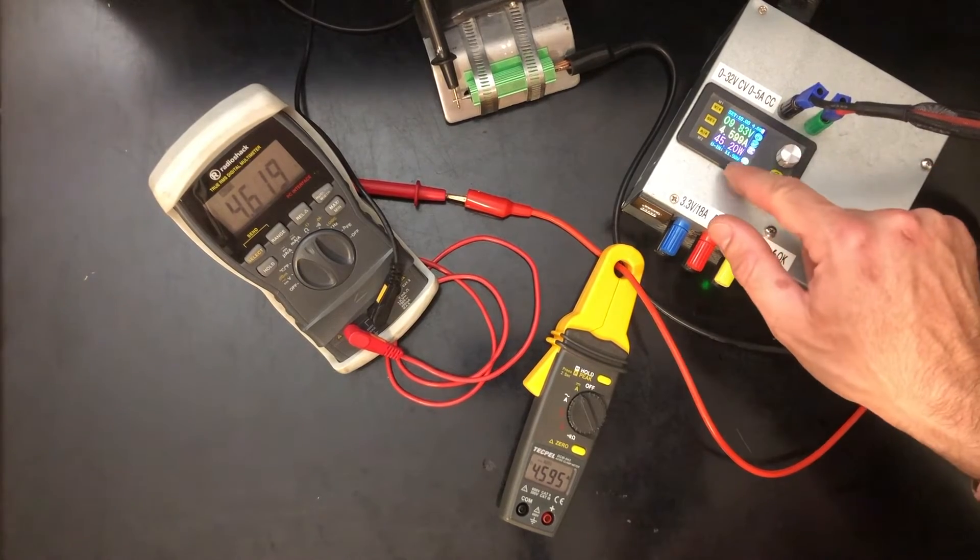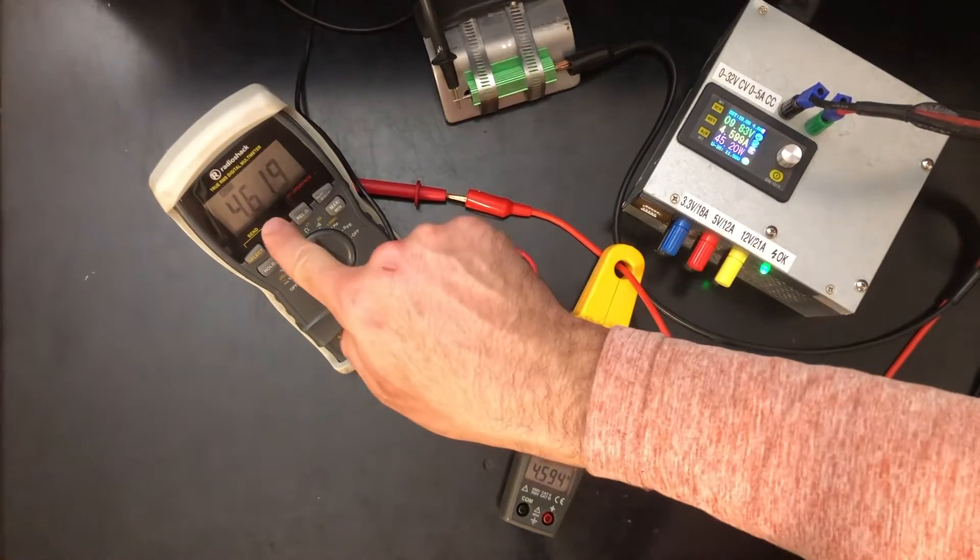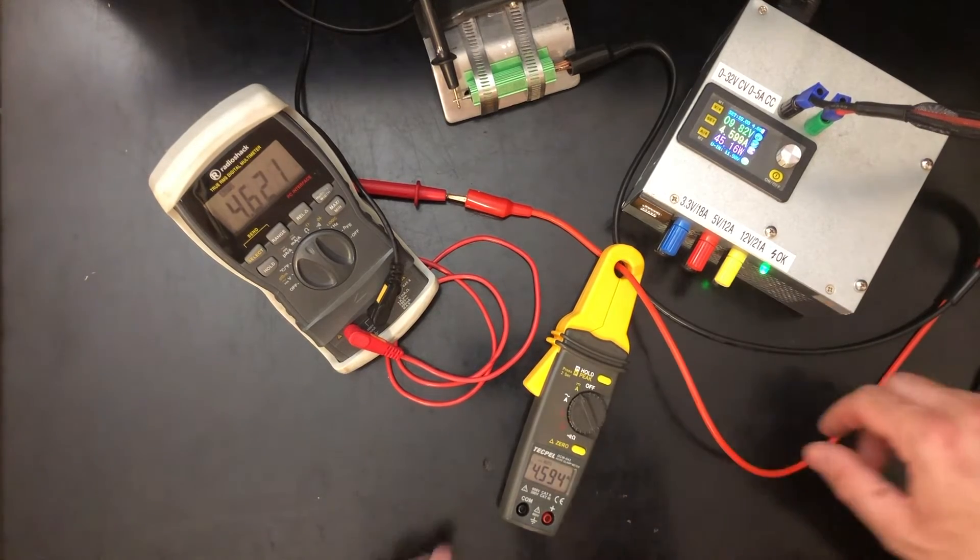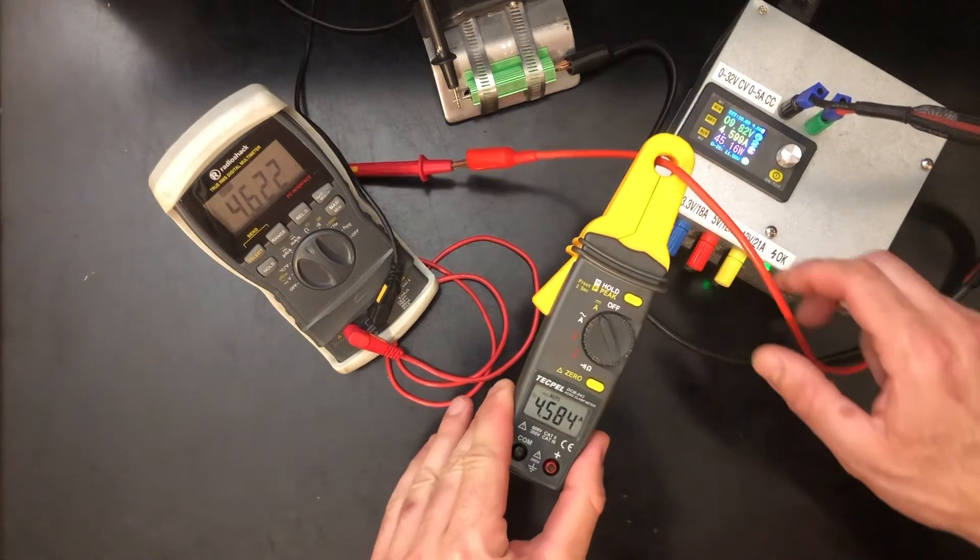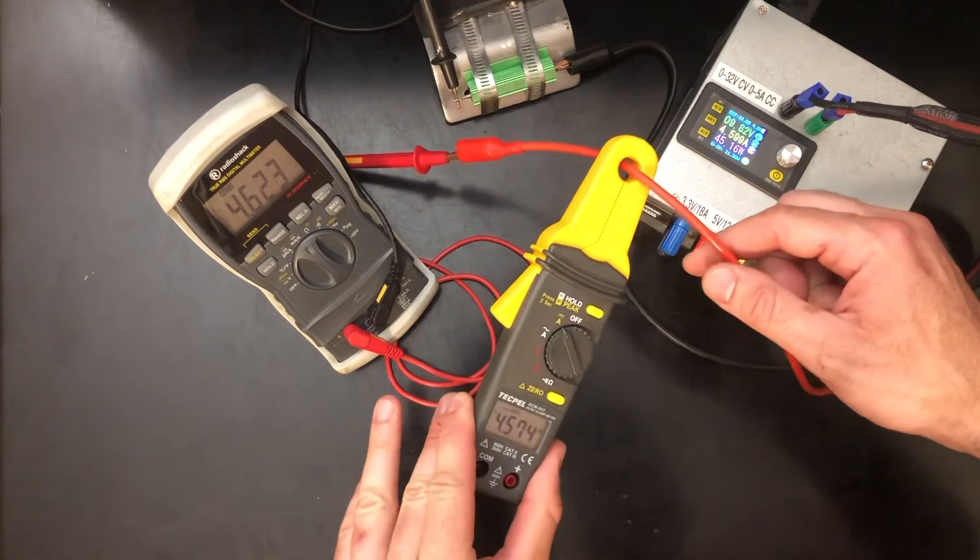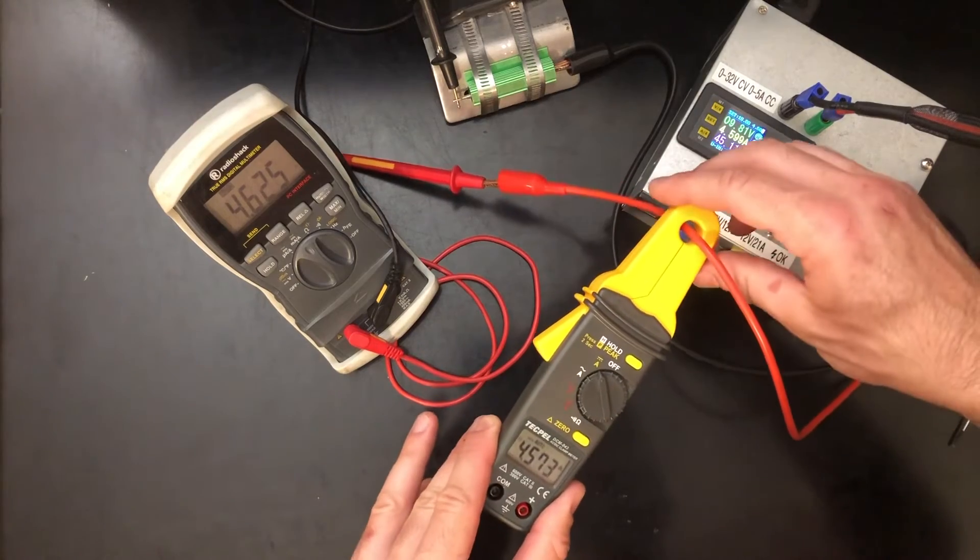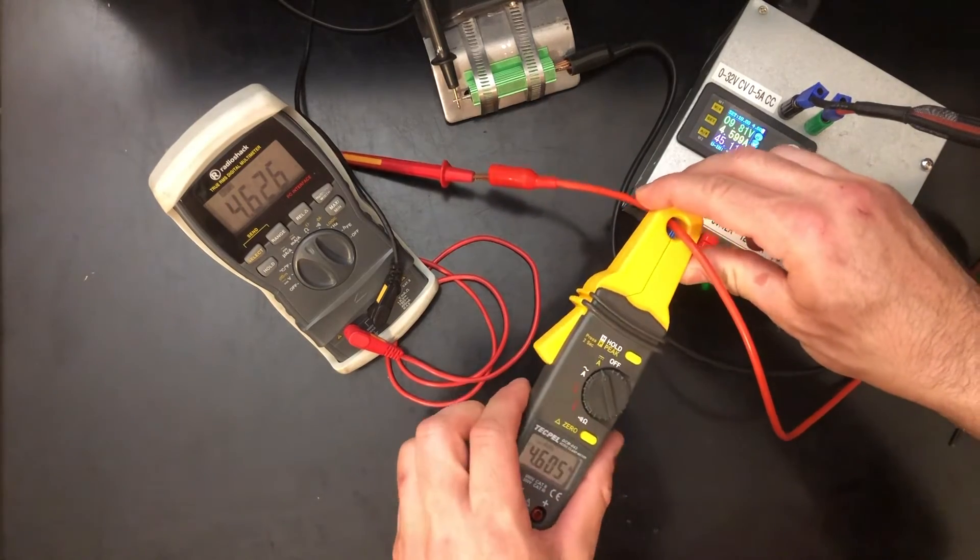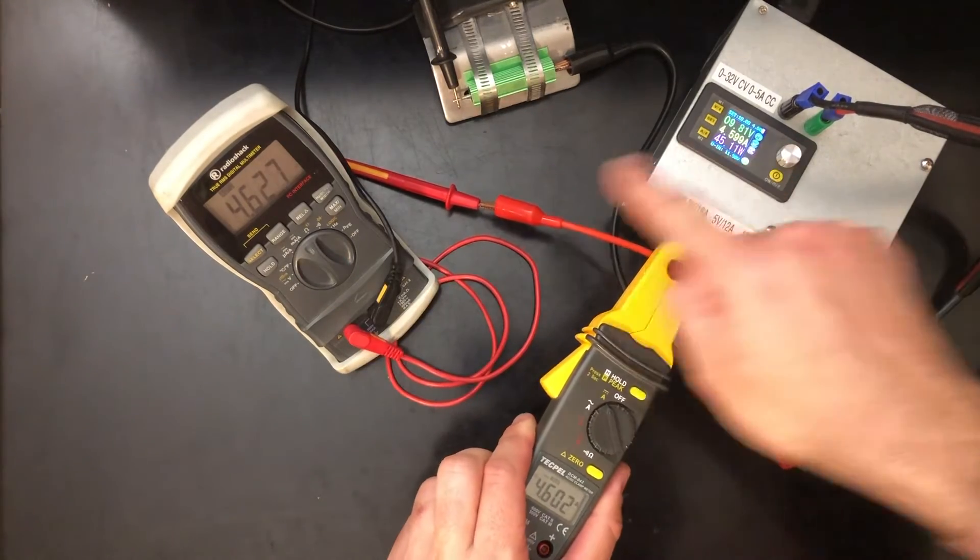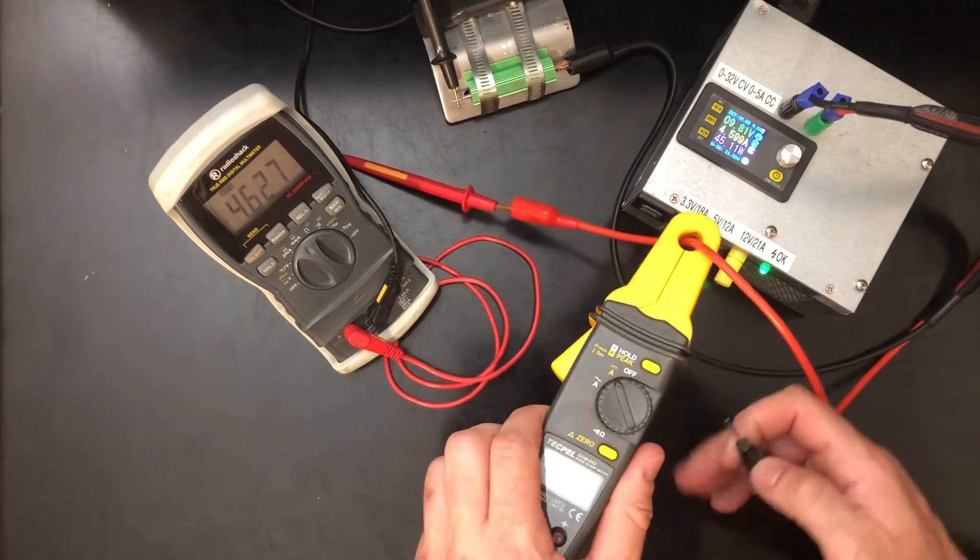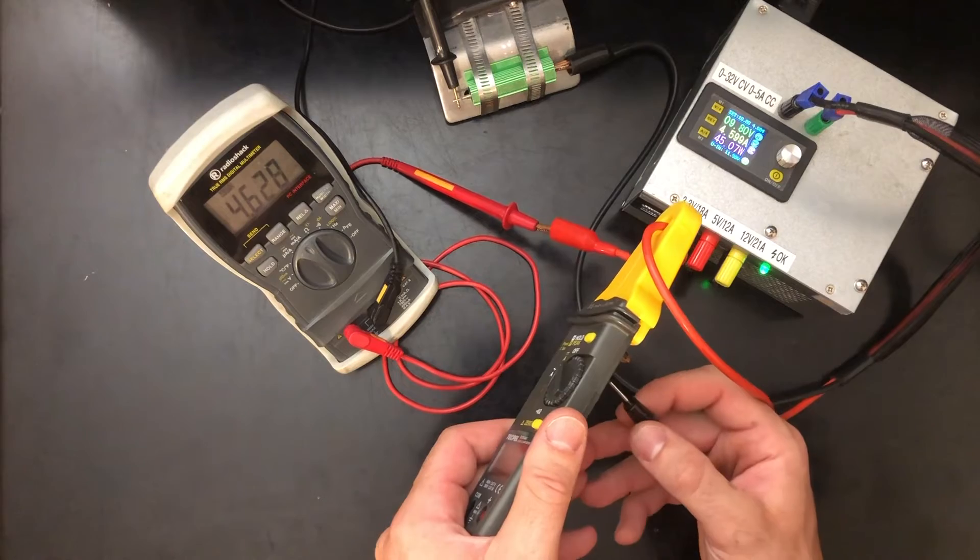So 4.6 amps according to this meter, 4.619 or 4.62 on this meter. And you can see we're at 4.57 on the clamp meter. So I think we can do a little bit better than that. Using these two references, I'm going to say that's right around 4.61 if I had to say in between the two. So I'll just give it one little additional tweak.